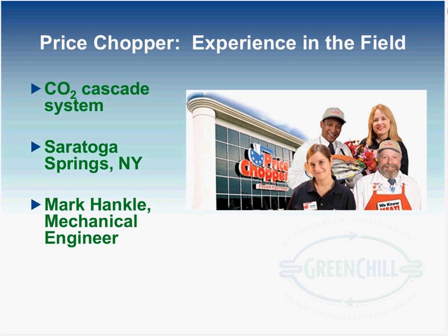If I'm not mistaken, the loss was earlier this year for the power outage. I want to say it extended over 6+ hours. One of the great things that we found out during that outage is we did have a full-size generator to provide backup power there. That was our first attempt at biodiesel there, so there was a little bit of a hiccup with the generator, but we've just resolved it. It maintained temperature without losing any CO2 for over 6 hours.